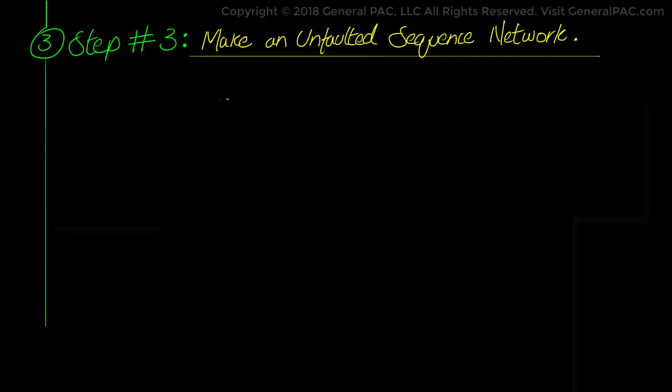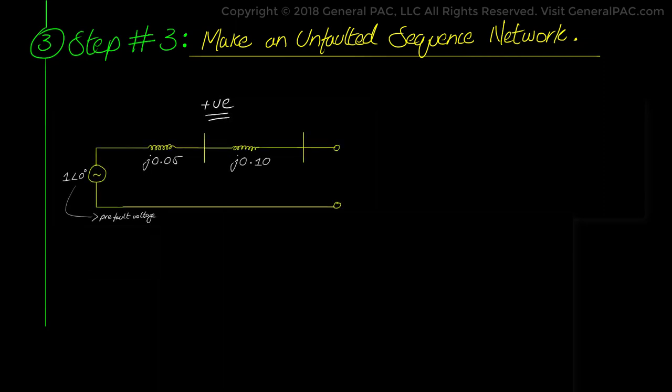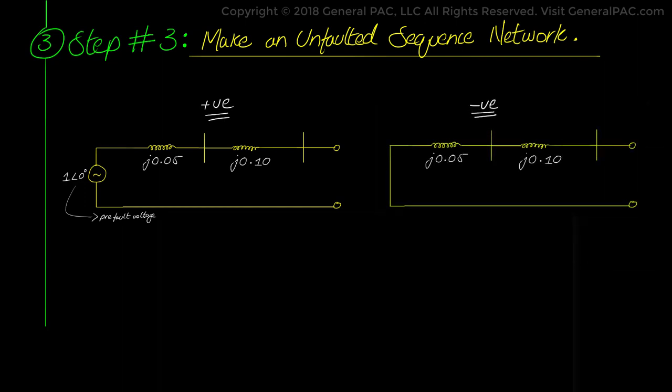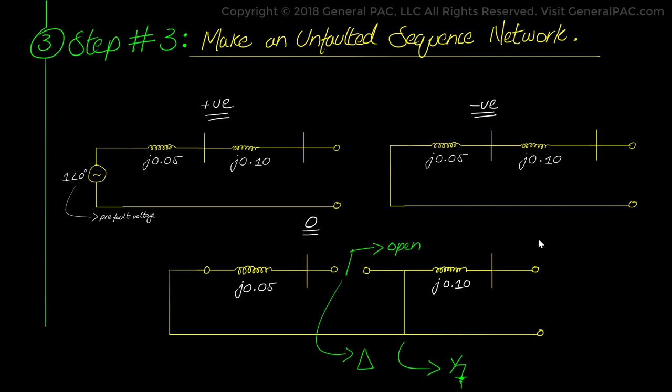Next we move to step number 3, which asks us to make an unfaulted sequence network from the per unit converted system in step 1. These are the individual sequence network diagrams which were converted in Part 2c of the series. Here we redraw the same networks. The positive sequence network diagram is indicated by the voltage source. The negative sequence network diagram is very similar but does not have a voltage source. The zero sequence network represents the delta-Y transformer with the high voltage side open and the low voltage side grounded.